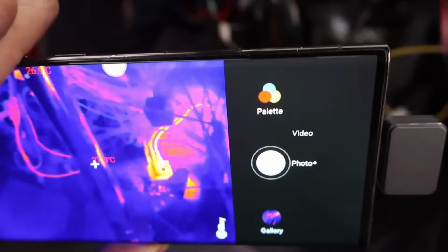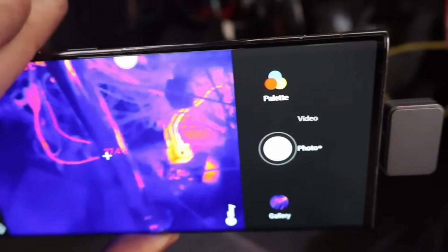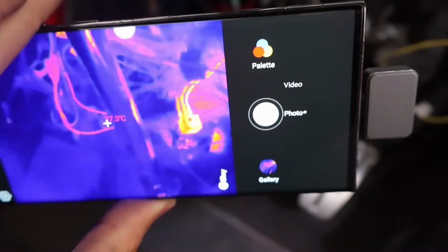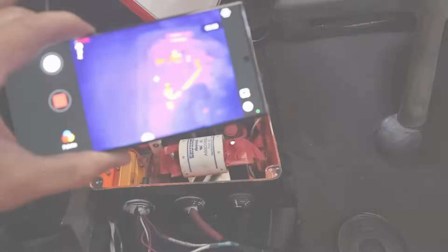I'm just checking to make sure nothing seems overly hot, any wires, but it looks like everything's good, just the relays are a little warm. This is inside the contactor box, the high voltage junction box, and again nothing's looking too warm, just right around 30 C, which is fine. That's great, one more thing crossed off the list.